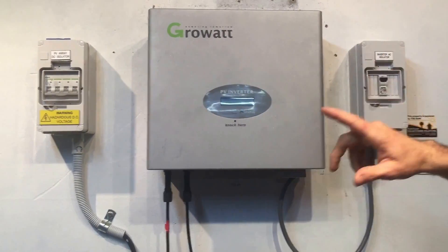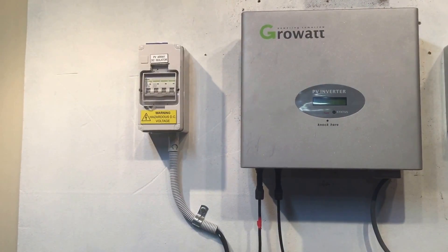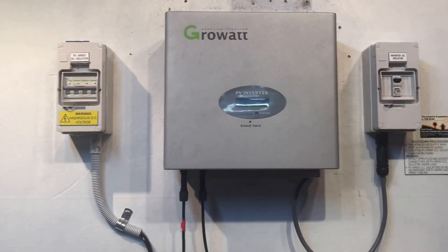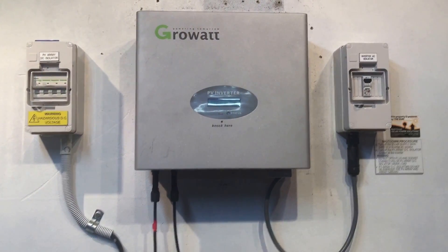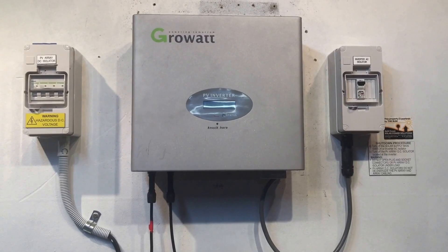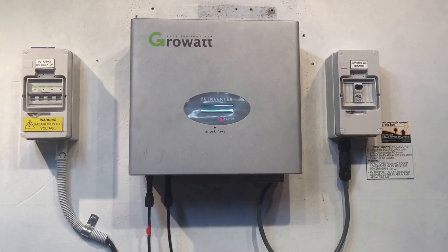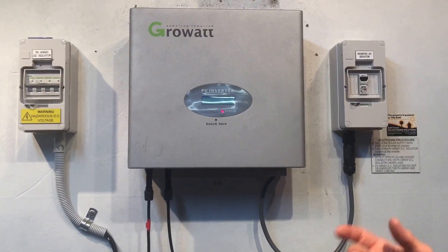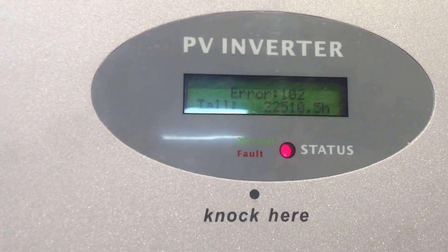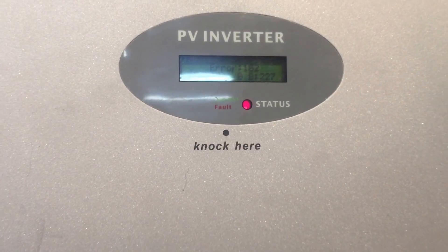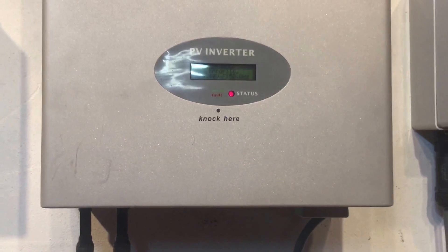Now we just turn on the AC and the DC. It doesn't matter what order when turning back on — it's just important when turning it off that it's in the correct order. It will go through a startup procedure. And look at that — it's gone straight back to Error 102, consistent fault. So this one's definitely got an issue that wasn't fixed by rebooting.